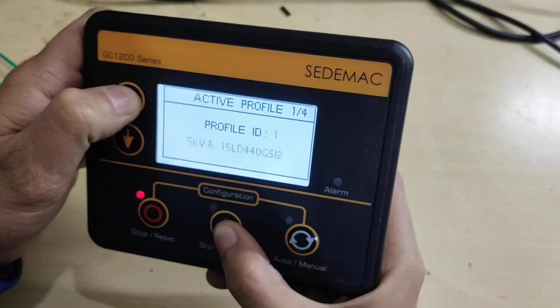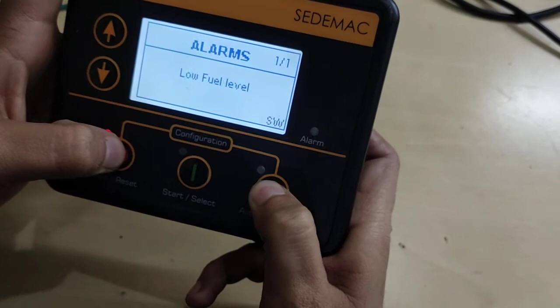Firstly, one needs to select the profile, like we select for a new controller. So after repair also you need to select the profile. Let us select the 10 kVA, and after pressing the same keys we can come out of it and then press start to confirm, and then we can again enter the controller programming mode.